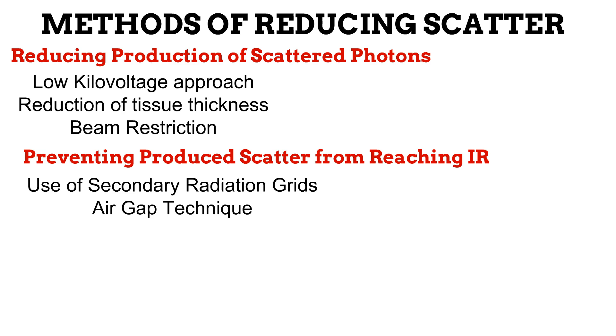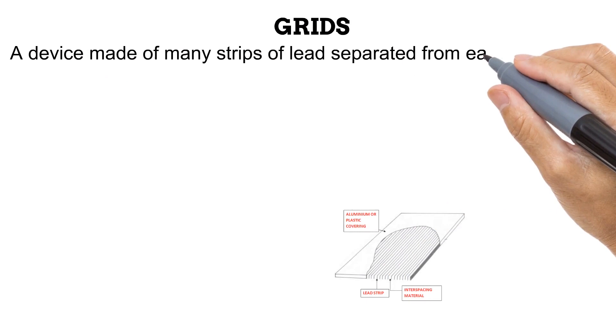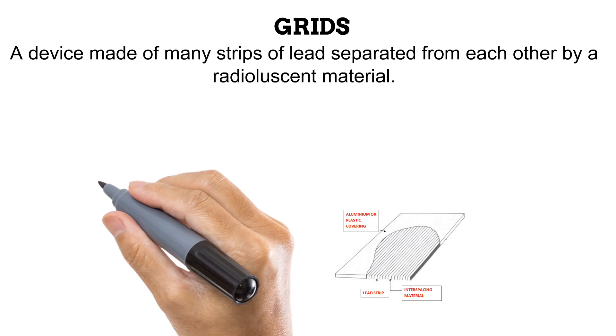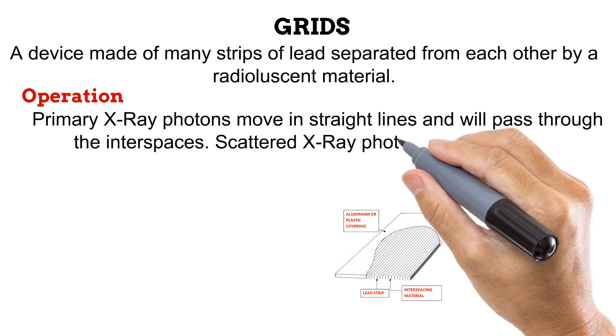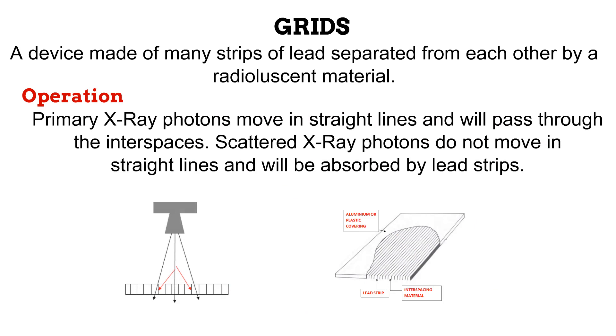We start with grids. A grid is a device made of multiple strips of lead that are separated from each other by a radiolucent material, also known as the interspacing material. The lead strips are arranged side by side. X-ray photons move in straight lines and will pass through the interspaces between lead strips, avoiding absorption by the lead. Scattered photons, however, do not move in straight lines, so most of them would not easily pass through the interspaces and would be absorbed by the lead strips.